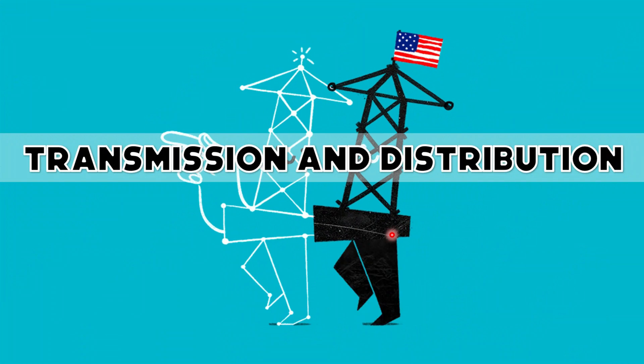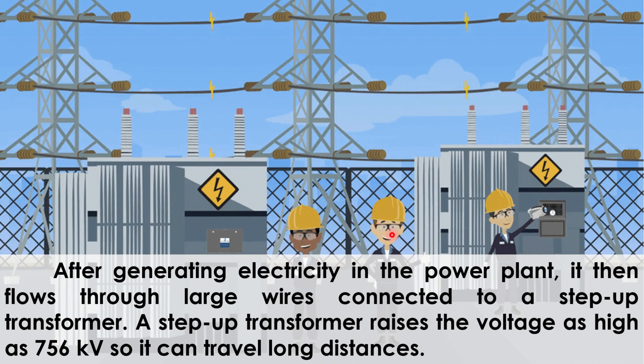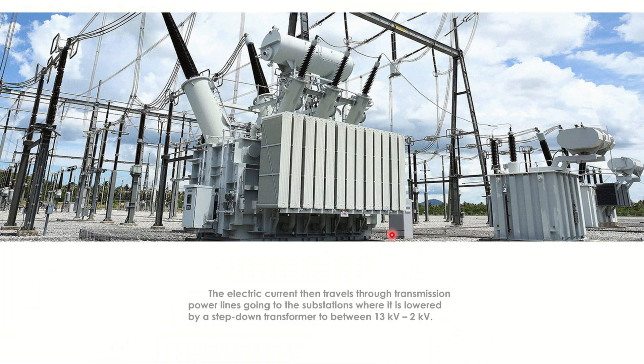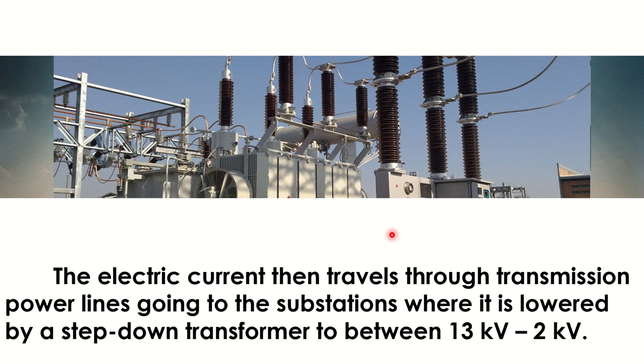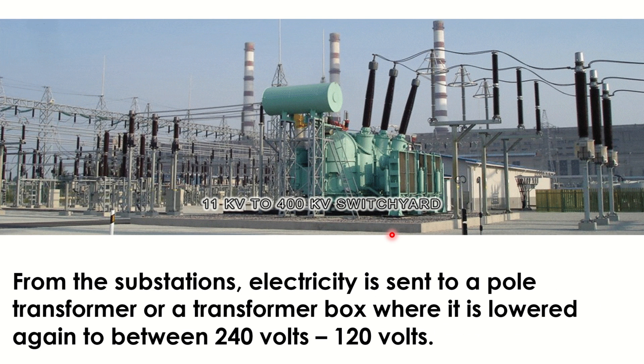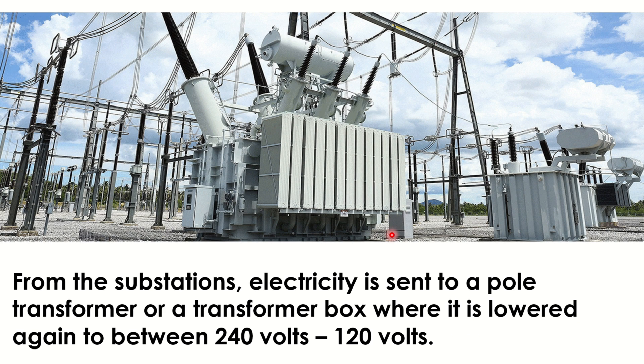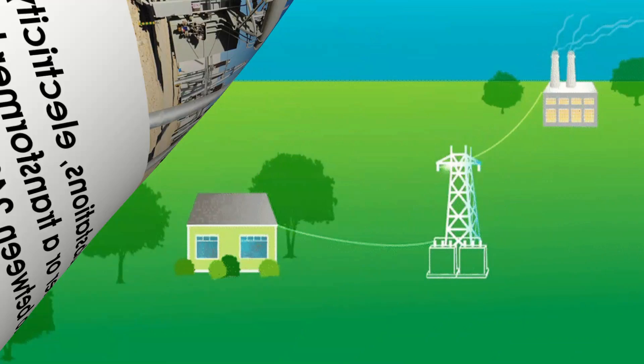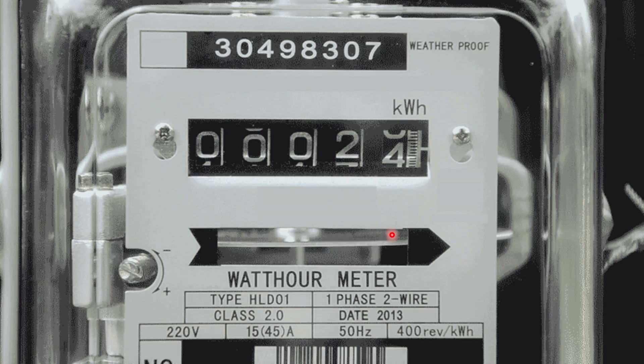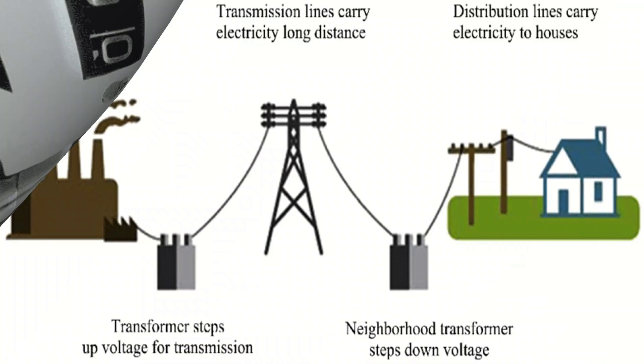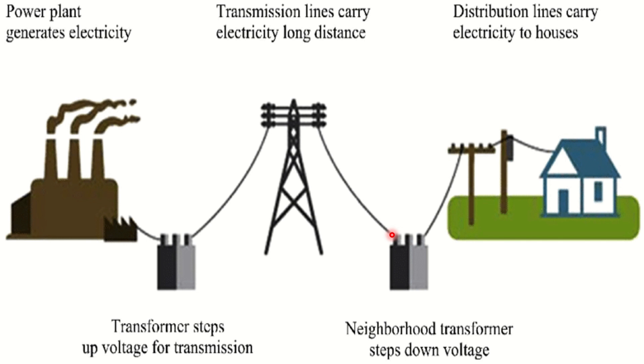Next is transmission and distribution. How does electricity reach you? After generating electricity in the power plant, it flows through large wires connected to a step-up transformer. A step-up transformer raises the voltage as high as 765 kilovolts so it can travel long distances. The electric current then travels through transmission power lines going to substations, where it is lowered by a step-down transformer to between 2 kilovolts and 13 kilovolts. From substations, electricity is sent to a pole transformer where it is lowered again to between 120 volts and 240 volts. It is from here where electricity comes into your home through a service box where your electric meter is located. Look at the photo showing the generation, transmission, and distribution of electricity.